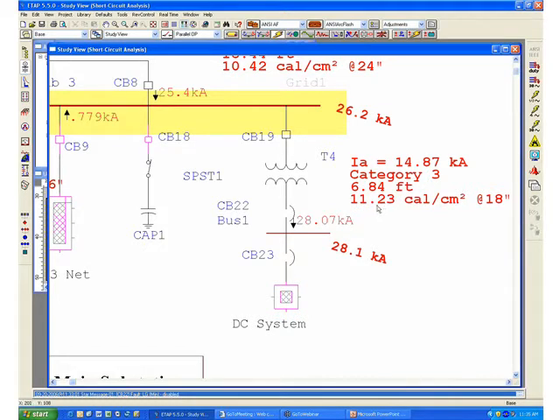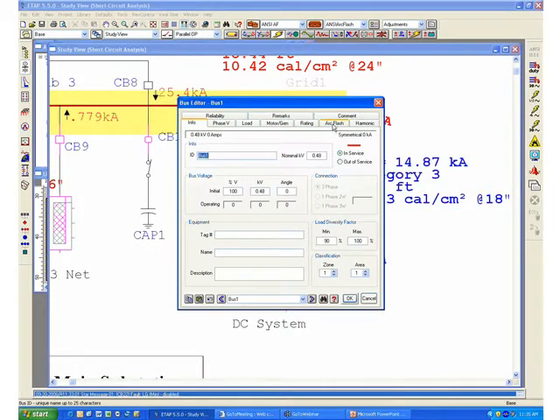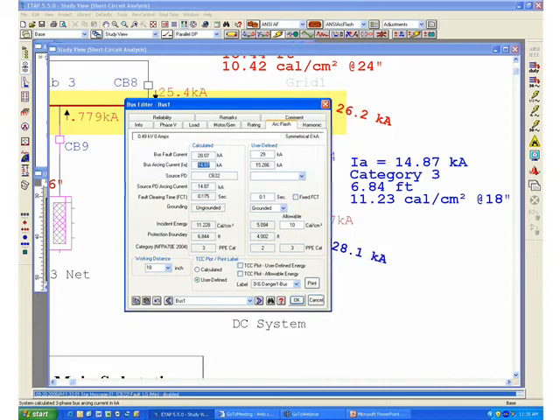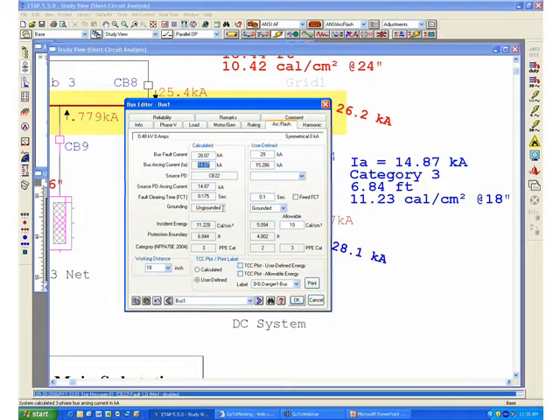You will automatically notice that the incident energy has increased quite significantly to 11.23. Our previous value used to be 8.66 calories per centimeter squared. If you go back to the bus editor, go to the arc flash page, you will now notice that the system has been configured or determined to be ungrounded. These are definitions that you can refer back in your NFPA 70E standard.